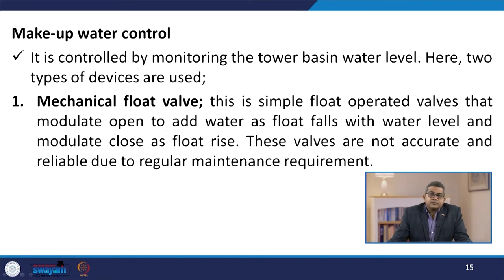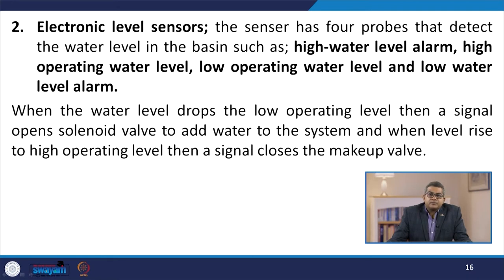The makeup water control is controlled by monitoring the tower basin water level. There are two types of devices used. One is the mechanical float valve — a simple float-operated valve that modulates open to add water as the float falls with the water level, and modulates closed as the float rises. These valves are not accurate and reliable due to the regular maintenance requirement. The second is the electronic level sensor, which has four probes that detect the water level in the basin: high water level alarm, high operating water level, low operating water level, and low water level alarm.